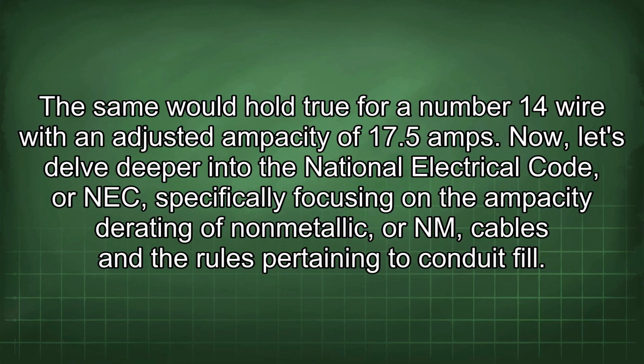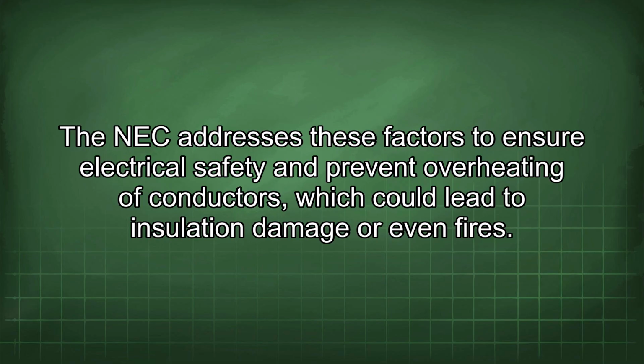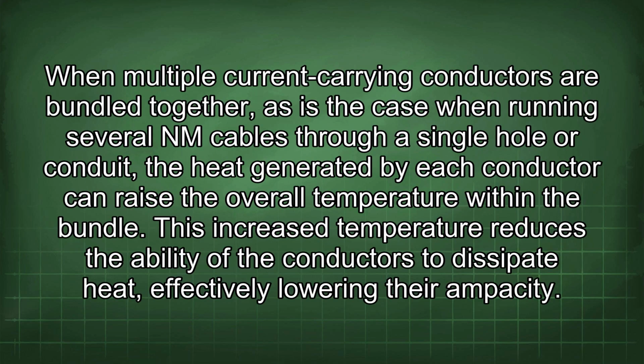Now let's delve deeper into the National Electrical Code, or NEC, specifically focusing on the ampacity derating of non-metallic, or NM, cables and the rules pertaining to conduit fill. The NEC addresses these factors to ensure electrical safety and prevent overheating of conductors, which could lead to insulation damage or even fires. When multiple current-carrying conductors are bundled together, as is the case when running several NM cables through a single hole or conduit, the heat generated by each conductor can raise the overall temperature within the bundle.